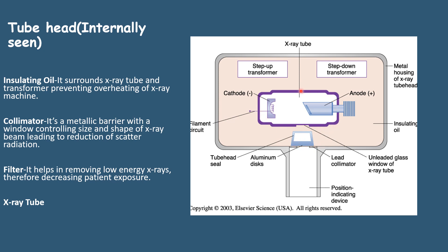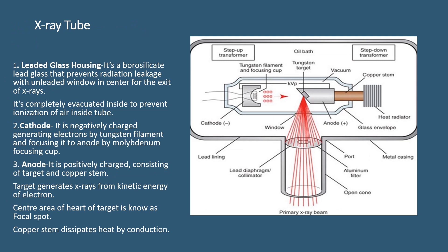This is the x-ray tube. The x-ray tube consists of a leaded glass housing, cathode, and anode. The leaded glass housing is made up of borosilicate lead glass. Its function is to prevent radiation leakage. It is completely evacuated inside to prevent ionization of air. This is the leaded glass which covers the entire x-ray tube. This leaded glass has a window — an opening from which the x-ray beams can pass through.